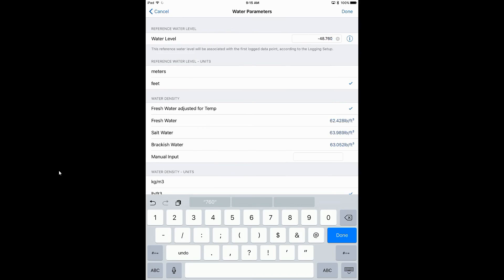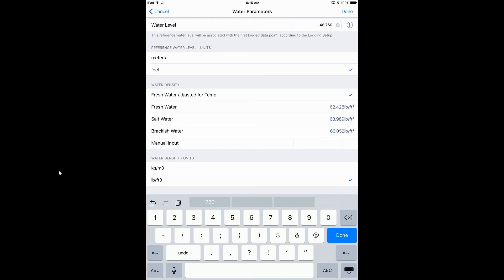We're also going to select what water density we want to use. For this deployment, we want fresh water adjusted for temperature — that gives us our best accuracy. But we could put in a standard fresh water value, or select salt water or brackish water. You can also manually enter a value if you have a density meter and take a density reading.